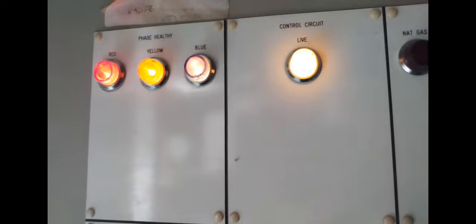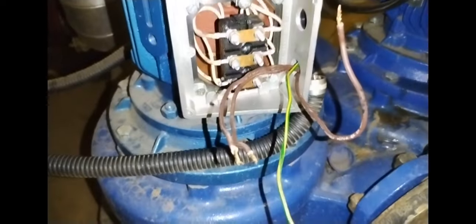It's nice when there's pressure gauges either side of the pump. It's not always practiced, but it does help. More plant room drawings here. It's good to study them. You can get different ideas for system design. On this system, there was one failed pump and 2 failed inverters. And so we're testing the pumps, and one of the pumps managed to work, wiring it straight in, but that was a temporary measure.